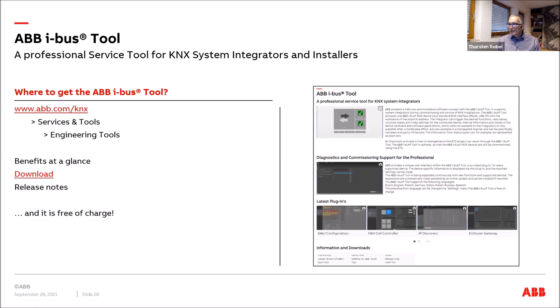From the Q&A: can a DALI group be part of another DALI group — like nested groups? A DALI group cannot be a member of another DALI group. However, if you want overlapping groups, you can use KNX group address assignment, which can be mixed with DALI groups in these components. Thank you for listening — please visit our booth at the KNX Experience. Goodbye!